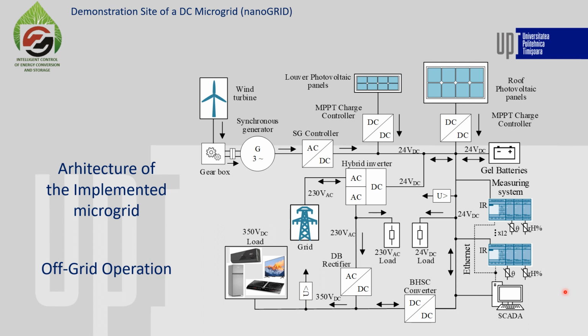Also, this is not presented in the diagram, but on the high voltage DC bus a capacitor bank is installed for more voltage stability. If only this diode bridge rectifier is used to supply the high voltage DC bus, at the first commissioning the capacitors are charged using a resistor, which is then short circuited.